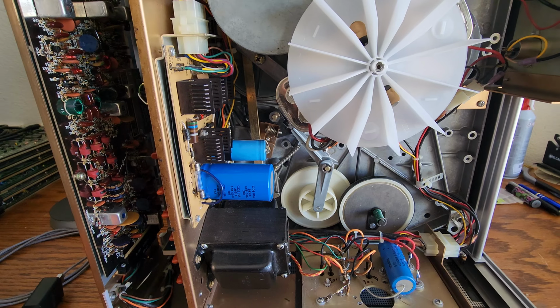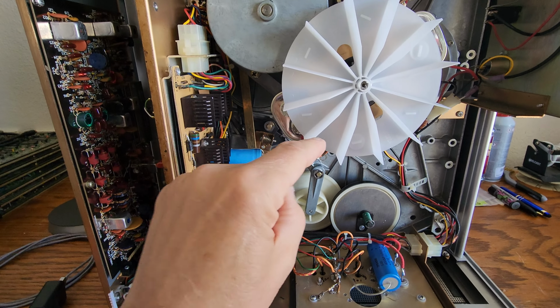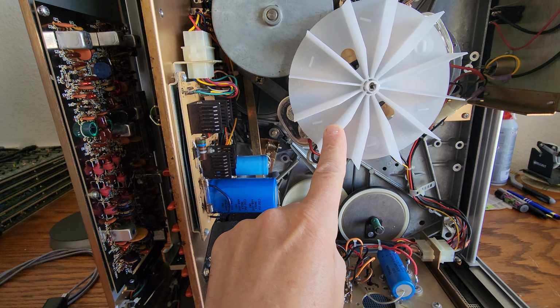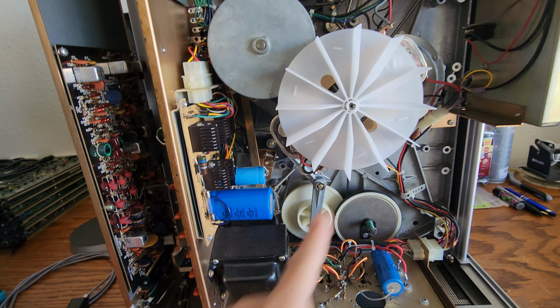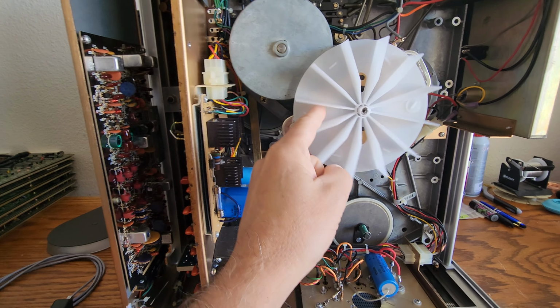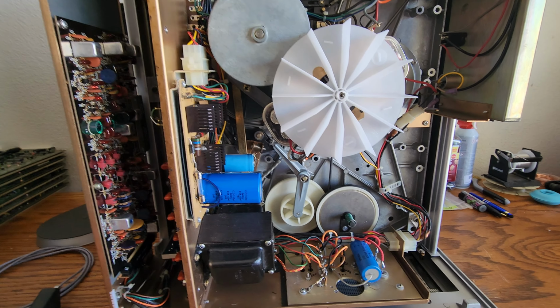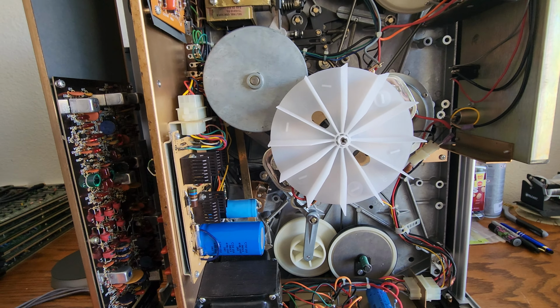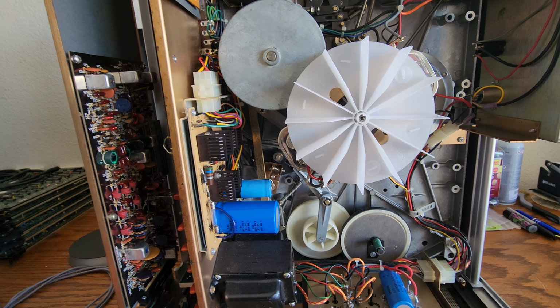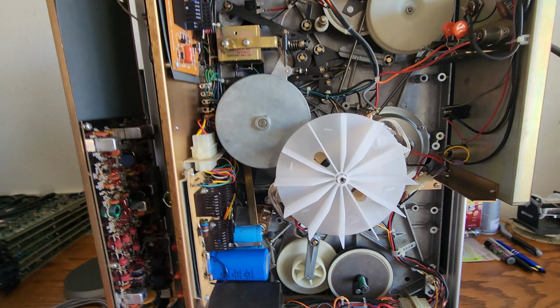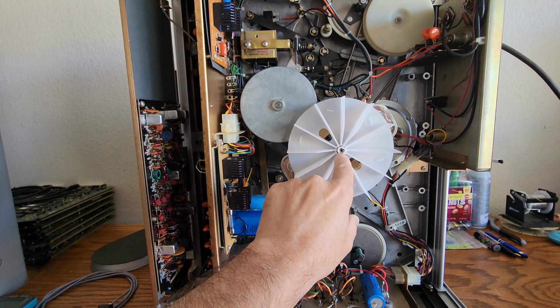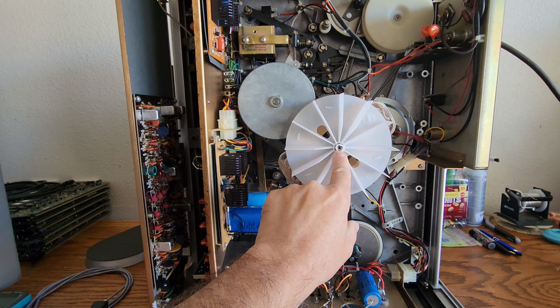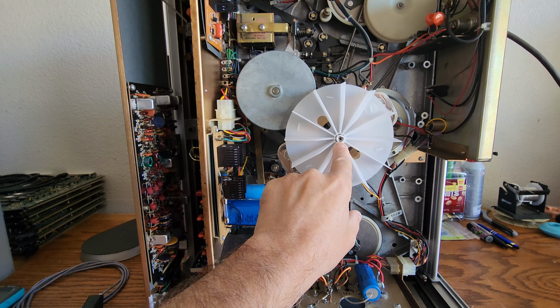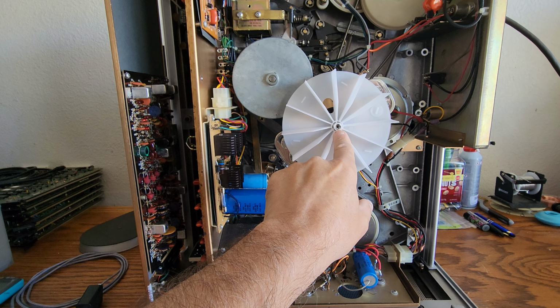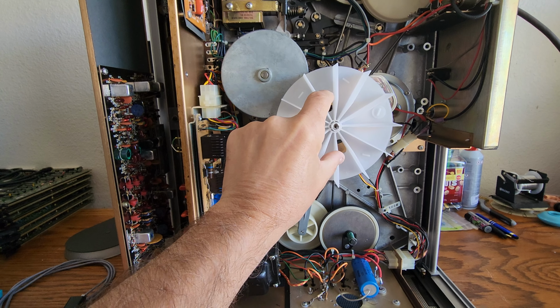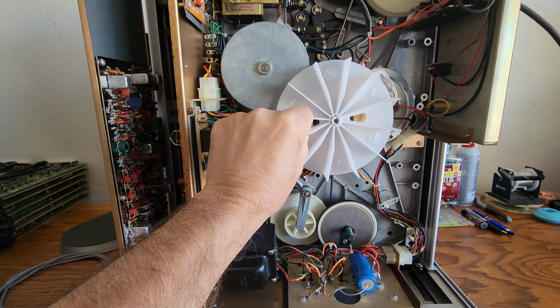Okay, now here's another thing which was quite tricky. The cooling fan below was broken. It would no longer mount, and it was cracked down the center. Of course you can't get these fans for these motors. So what I did is I went down to Home Depot, and this is a fan that came off of the little motors for exhaust fans in your bathroom. I drilled that out because the shaft was too small, got it dead center, and of course it drilled out perfectly. And I put some JB Weld glue on the shaft at that point and slid it in right where it belongs. This thing is solid. It ain't going anywhere. It's not ever going to come off.